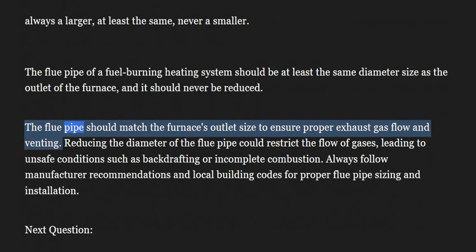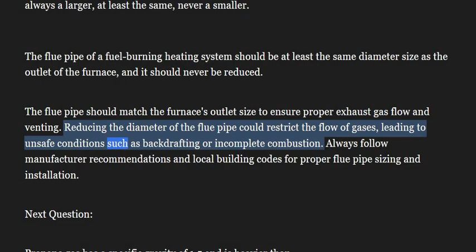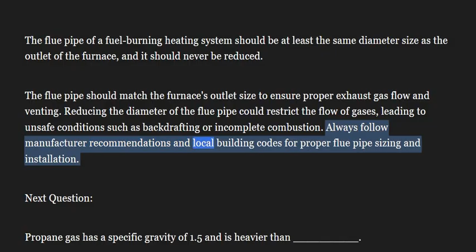The flue pipe should match the furnace's outlet size to ensure proper exhaust gas flow and venting. Reducing the diameter of the flue pipe could restrict the flow of gases, leading to unsafe conditions, such as backdrafting or incomplete combustion. Always follow manufacturer recommendations and local building codes for proper flue pipe sizing and installation.